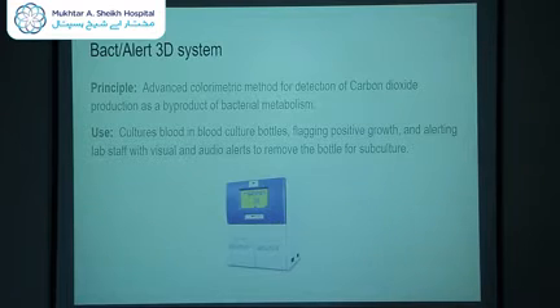This is the BacT/Alert 3D system that we have acquired. The principle is based on an advanced colorimetric method for detection of carbon dioxide. All bacteria, after using the media, produce carbon dioxide as a product of their metabolism. This is detected by a sensor at the bottom of the blood culture bottle which changes color, and that is detected by the machine, which then alerts staff with visual and audio alerts to remove the bottle for subculture.